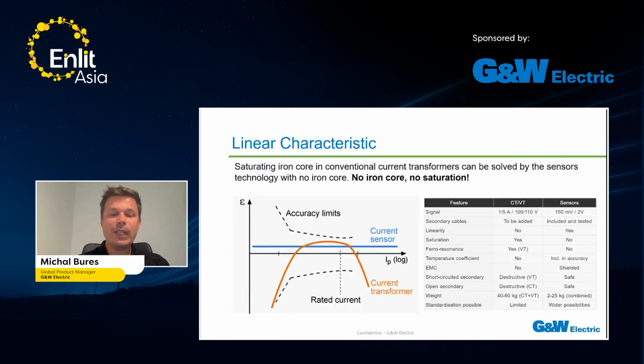thousand amps. As I mentioned, one of the main advantages of the sensor compared to a conventional instrument transformer is linearity, because there is no iron core, and no iron core means no saturation, and no saturation means linearity of the output signal. So exactly what you see at the input, you will see on the output. So it's very, very efficient. So if we just go through the features very quickly and compare CTs, VTs, or CT-PTs with a sensor, the signal in this case is very low.